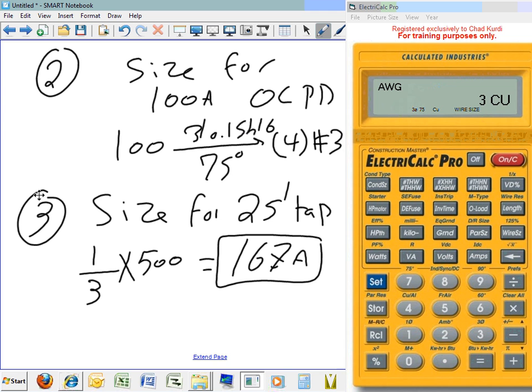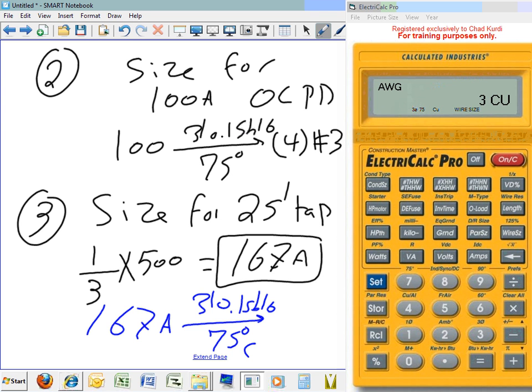Okay, let's go size that baby. So 167. I'm going to take 167 amp to 310.15(B)(16). Under which column? 75. Why? Because it's more than 100, and I also am telling you it's 75 degree terminals. What would you get? Number 2. 4 conductors or aught. 2 aught. 2 and an aught. 2 aught. 4 conductors, 2 aught.